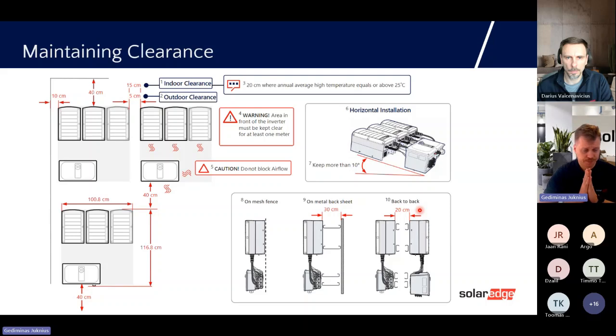With the inverters, it doesn't matter whether it's a residential or commercial inverter. Please read the manual and check the clearance for heat dissipation. Do not block airflow. Power electronics has one enemy, and it's heat. So if you want the inverter to work through the warranty period and longer, make sure it has a chance to cool down. Whether you're installing indoors or outdoors, there are different distances. It's all in the manuals, easy to check.